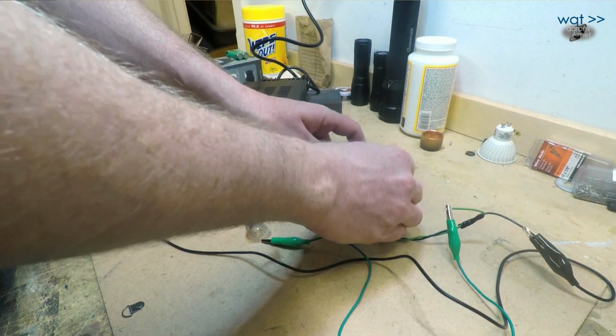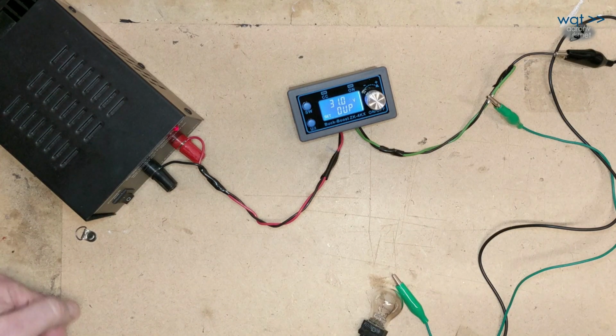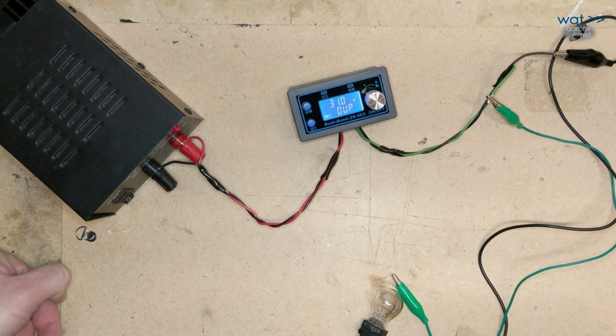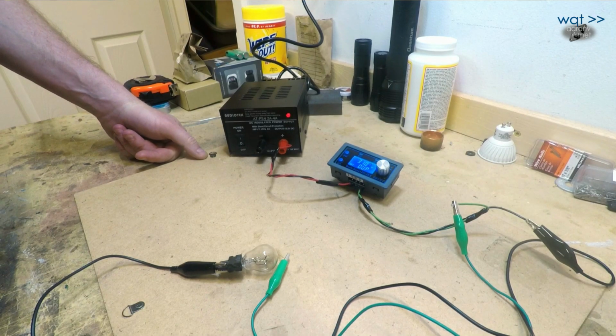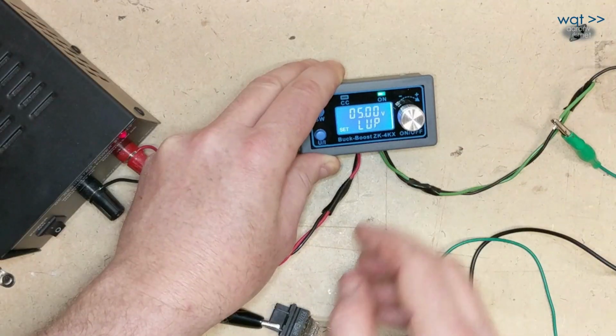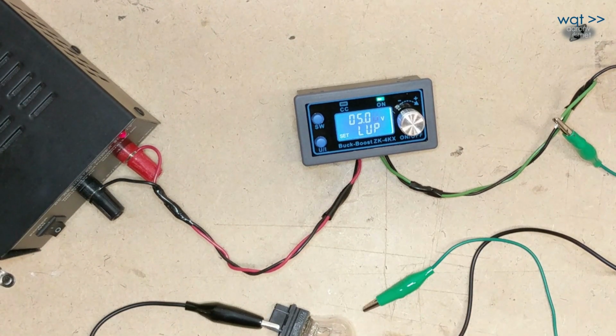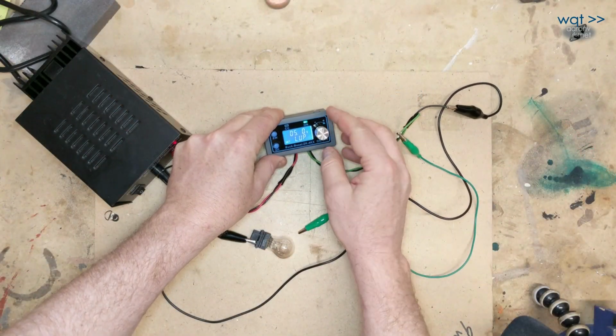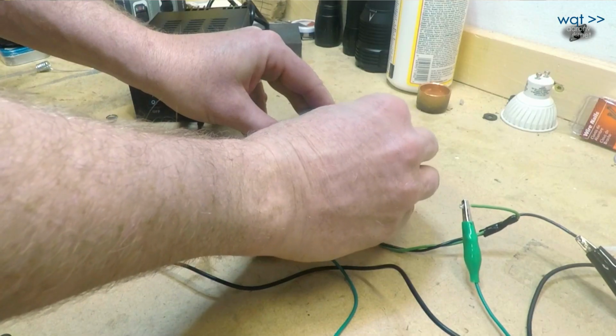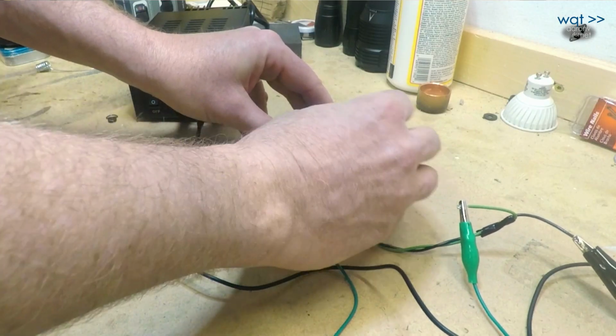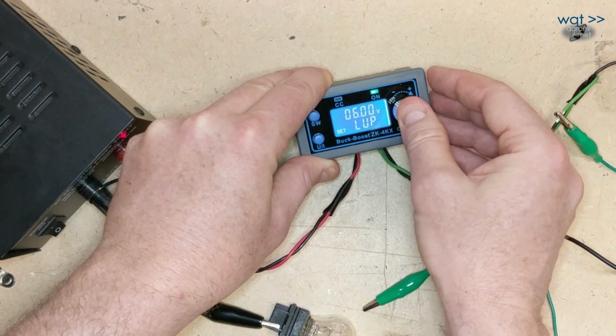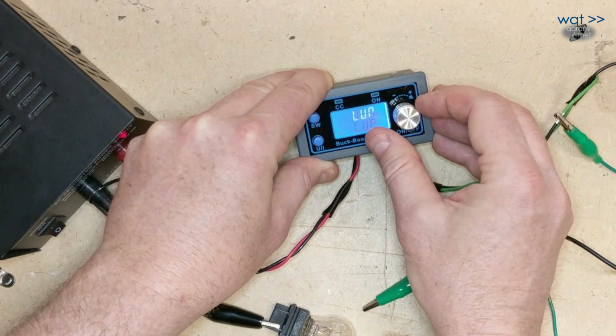Output upper, same thing - I don't want my voltage to be above a certain limit or I won't start up. So for example, if I never want to go above 20 volts, I could set that. But notice how that last digit is flashing. If I press this, I start to cycle through them, so now I can scale at the tenths rather than the hundredths, or I can scale at the 1 volt level, or I can go all the way up here.